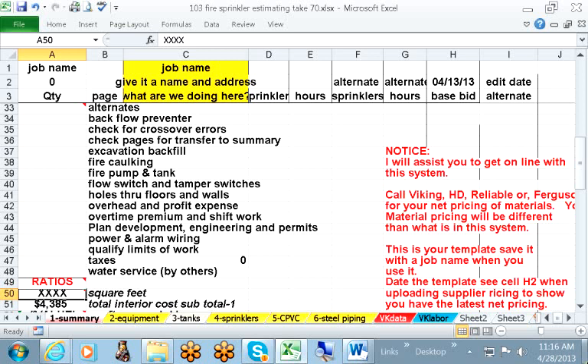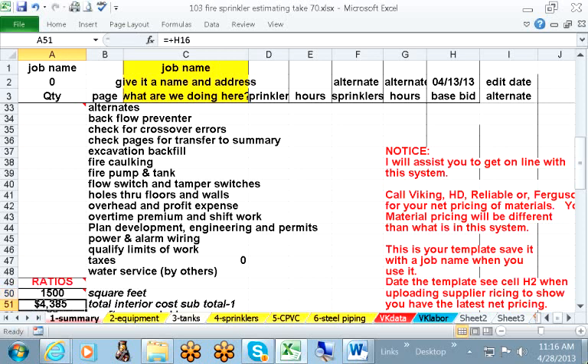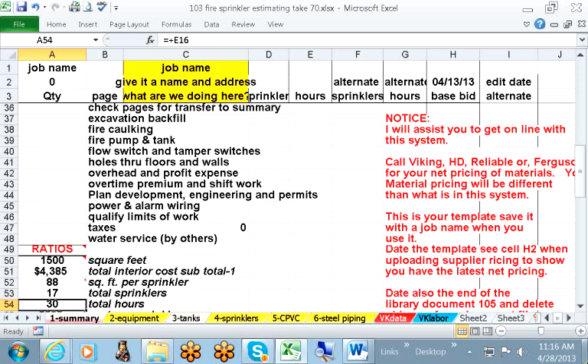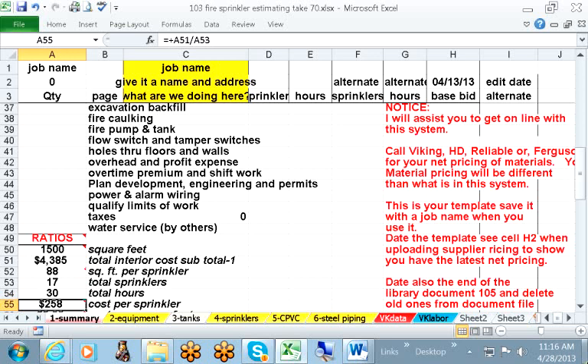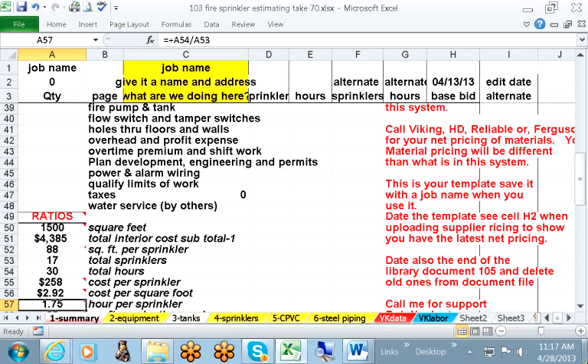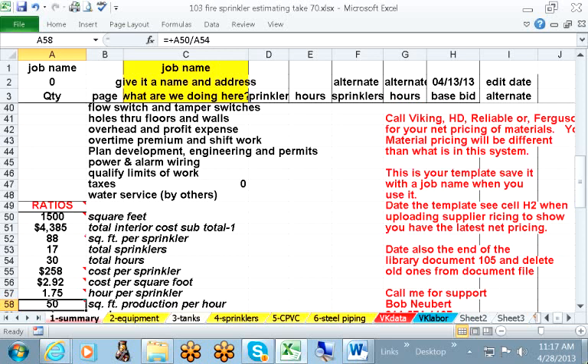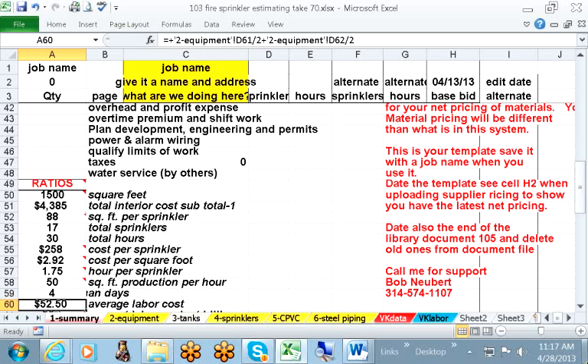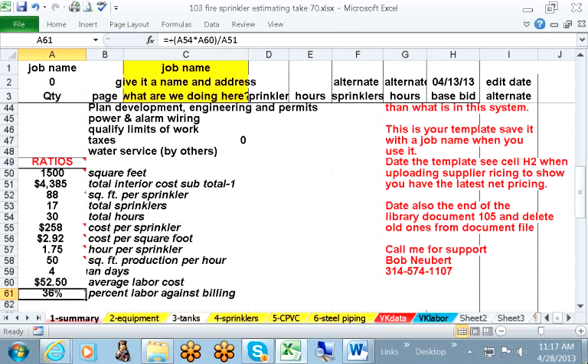We have a ratio of considerations, and we know that the house has got 1,500 square feet, which gives us some ratios. 88 square feet per sprinkler, 17 sprinklers, 30 total hours, $258 per sprinkler, $2.92 per square foot, 1.75 hours per sprinkler, 50 square feet of production per hour, 4 complete days, $52.50 is the average labor cost, and 36% labor ratio of the total cost.